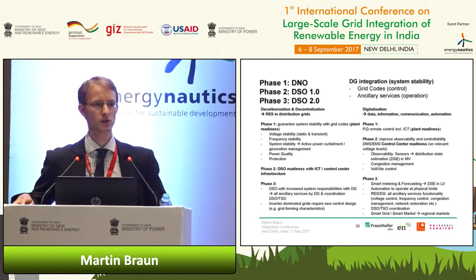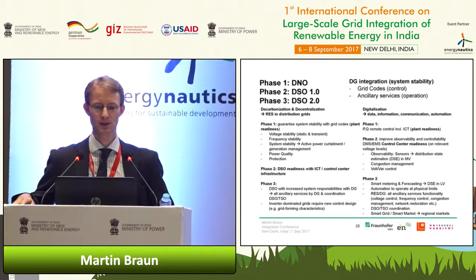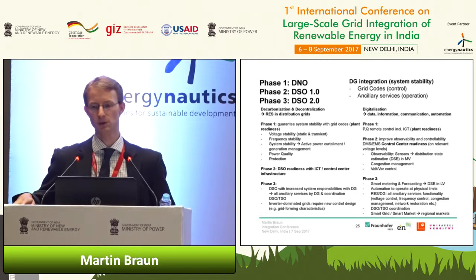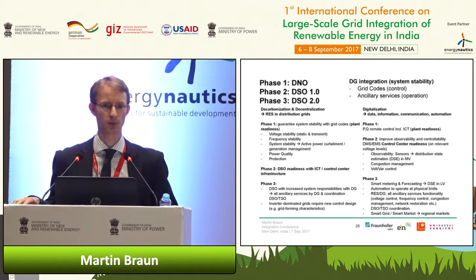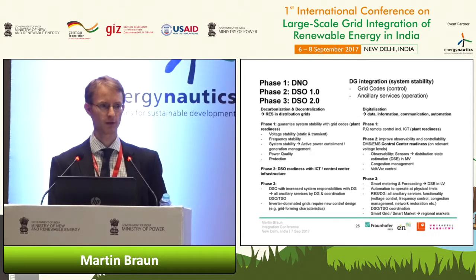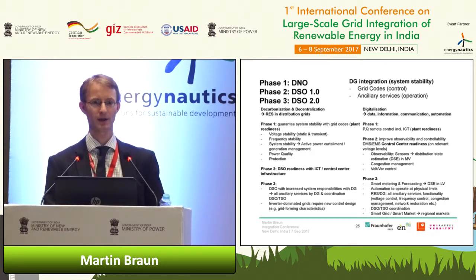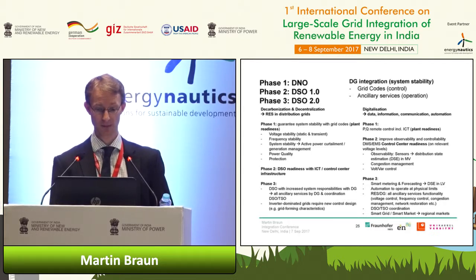Everything is with grid codes, nothing more. You need to design voltage stability, frequency stability, system stability with active power curtailment, also some requirements for power quality and protection. This is sufficient for phase one, and this is the so-called plant readiness level. So all the systems you install should be ready to do that, even if it's not required at the first phase, but you need it in the next phases, and then it should be prepared.